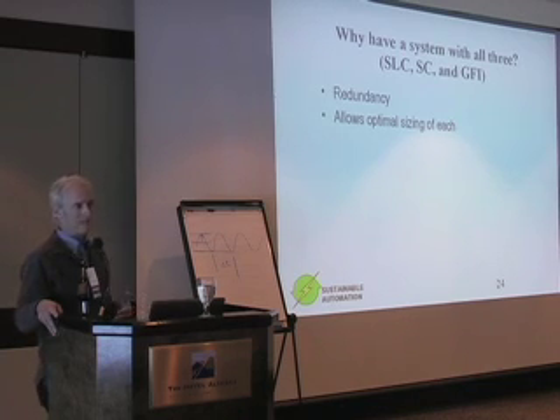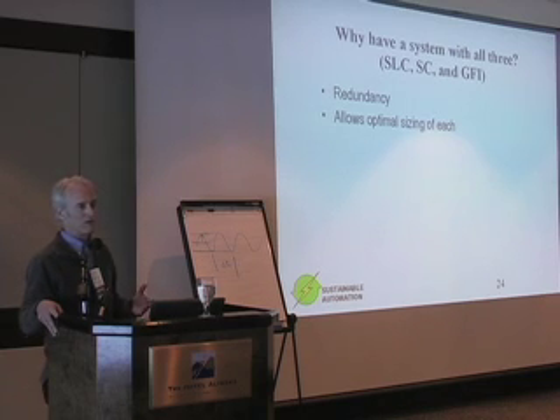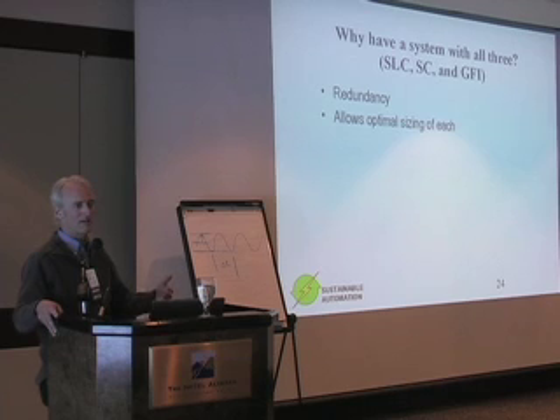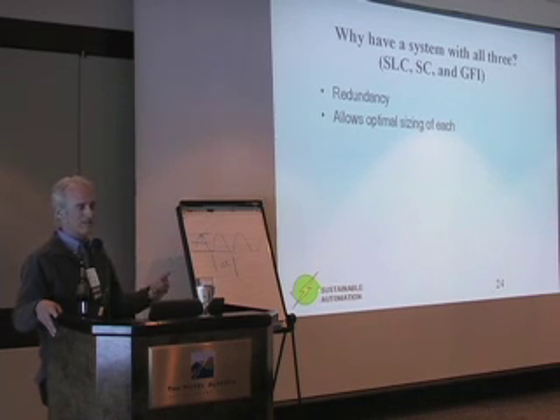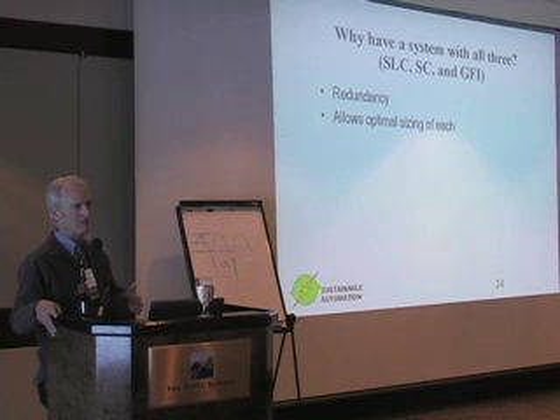Reliability to utility, reliability of power supply is everything. So if you're taking the extra step of installing the battery inverter system or whatever form of energy storage, you've already sunk a large amount of money into that system. That tends to be the most expensive component. For a relatively modest, I mean, it's not cheap, but it's a very reasonable incremental cost, you can have the secondary load and synchronous condenser combination as well, and you need the secondary load anyway, as I said, to absorb excess power. That provides you a margin of extra reliability in case the inverter faults for some reason.